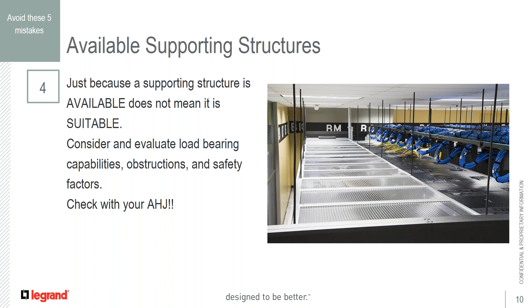Here's an example. We very often encounter situations where the planned support structure presents a conflict with other trades once on site. It's not uncommon for the installation team doing the containment to show up on site and have conflict with other trades, such as cabling contractors, plumbers, HVAC, and electrical, who are trying to install according to the drawings they're working from, things like basket tray, overhead power, and such. So making these on-the-fly changes can cause delays, frustration, conflict on the site, and least desirable of all, costly change orders.